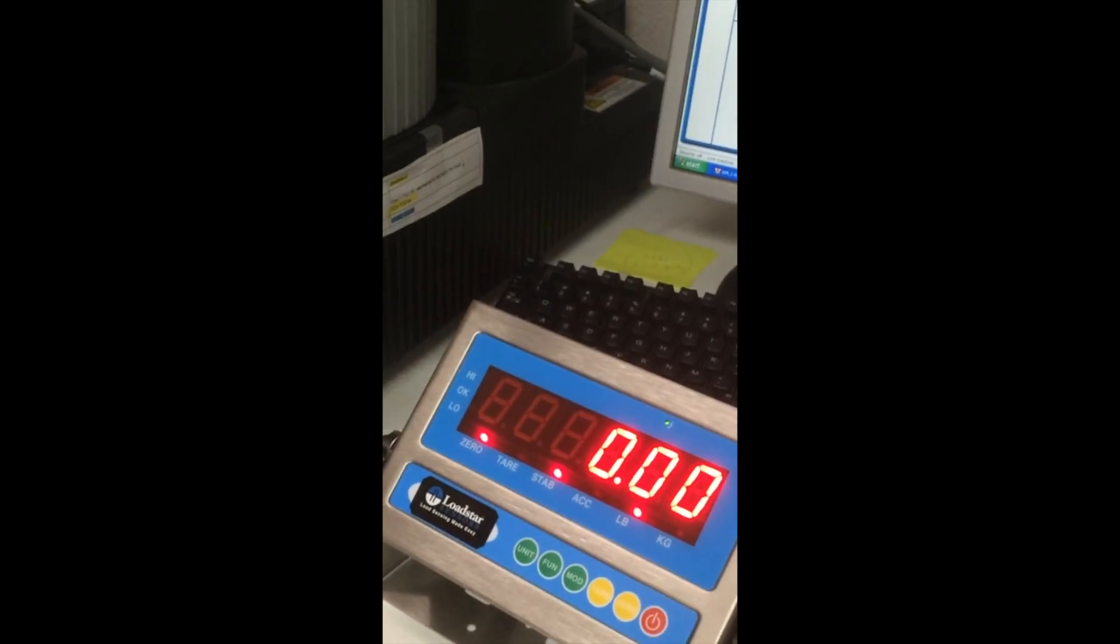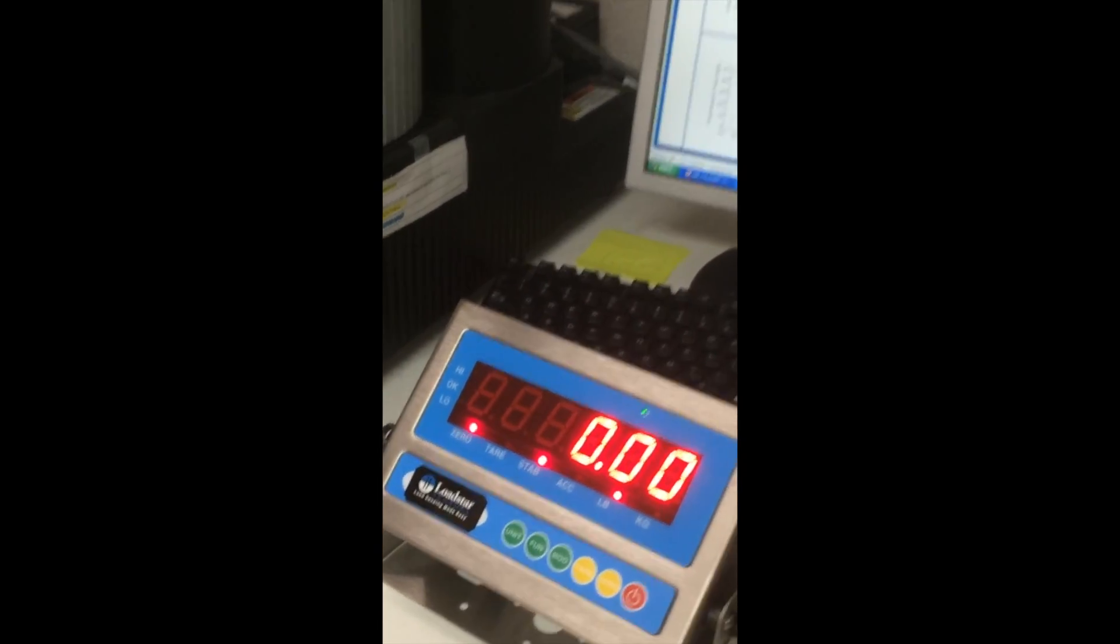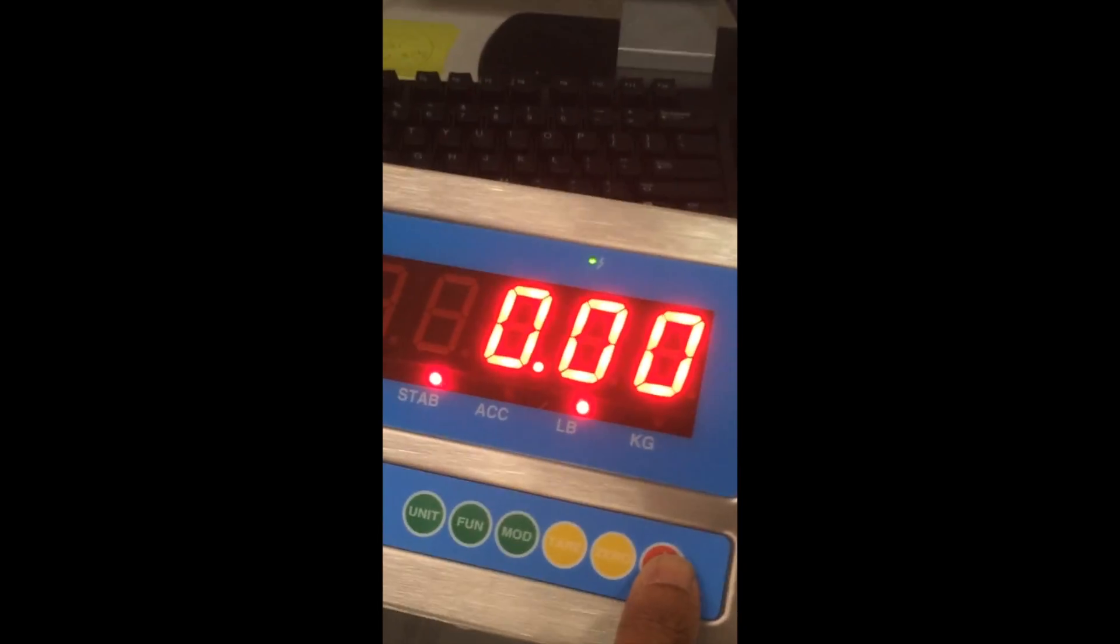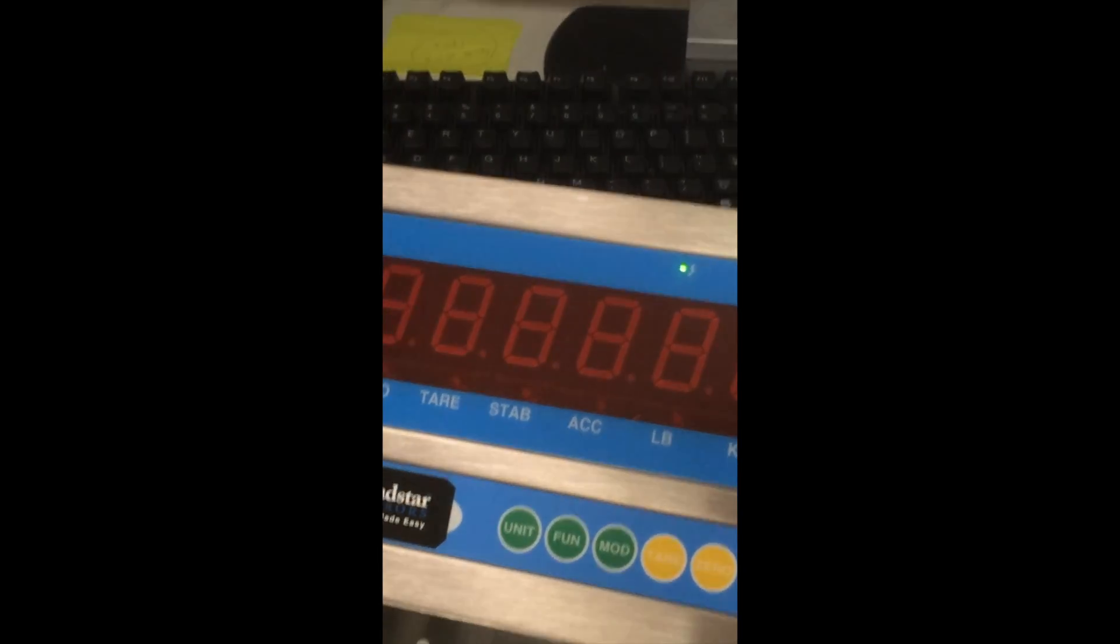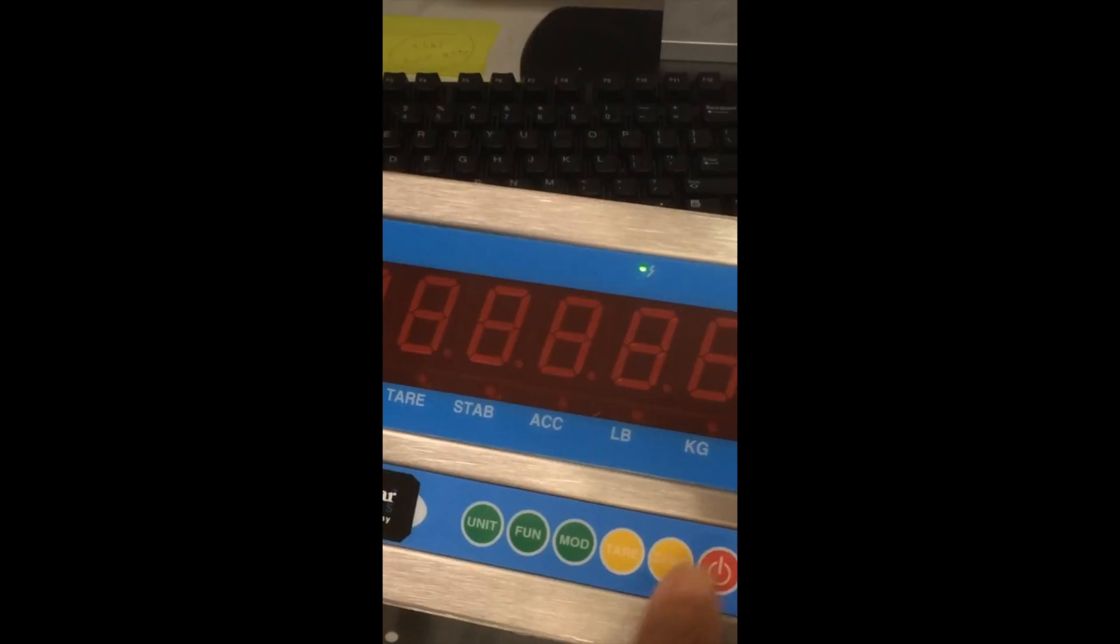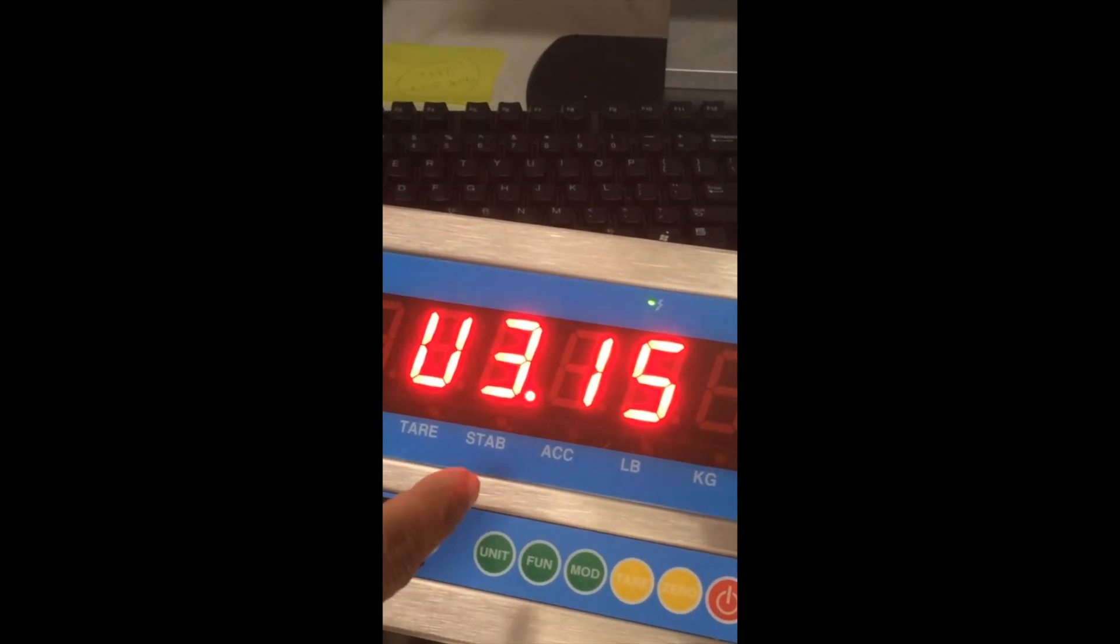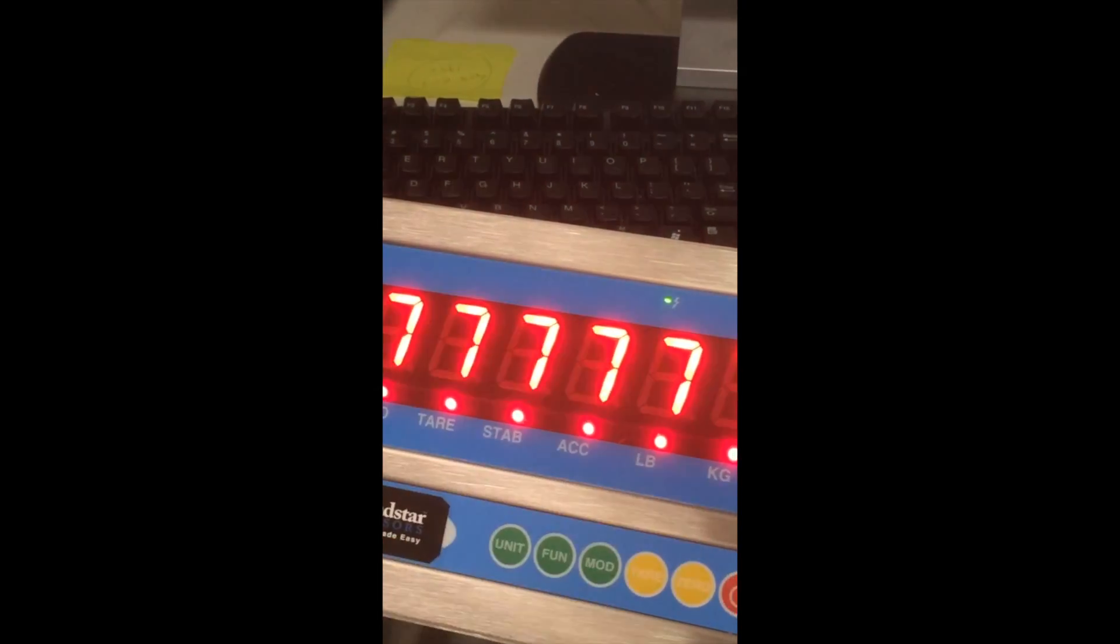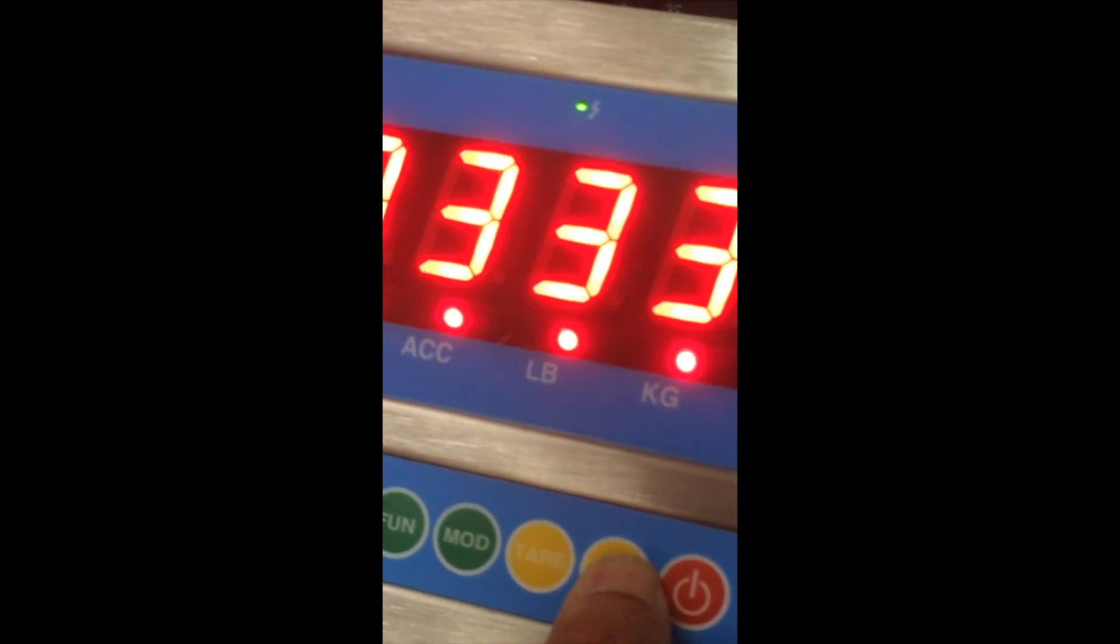The first thing you have to do is go into the setup mode to calibrate. To do that, you power it down first, power it back up and while it is counting down or counting up like this, press the 0 key.